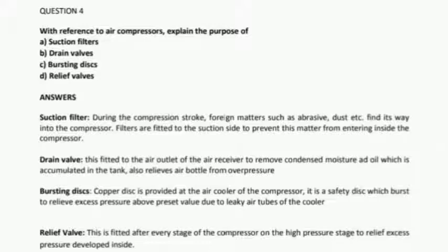The bursting disc is provided at the air cooler of the compressor. It is a safety disc which bursts to relieve excess pressure above preset value due to leaky air tubes of the cooler. The relief valve is fitted after every stage of the compressor on the high pressure stage to relieve excess pressure developed inside the air compressor.